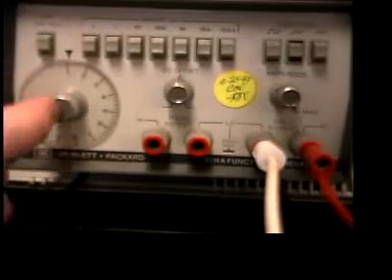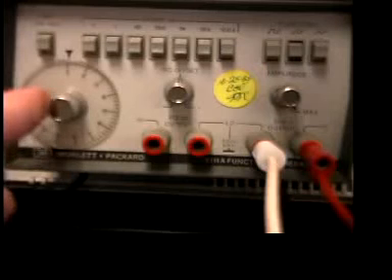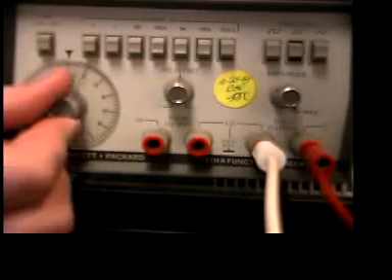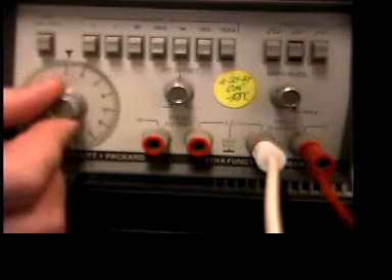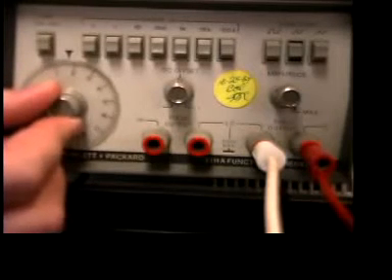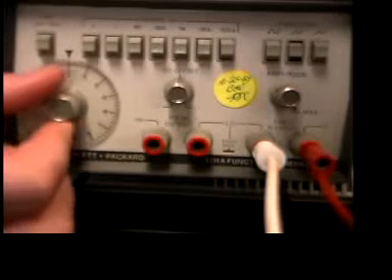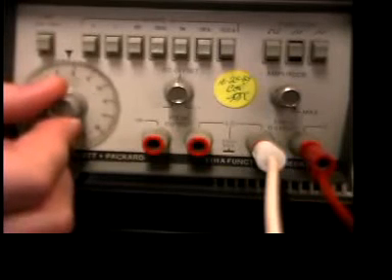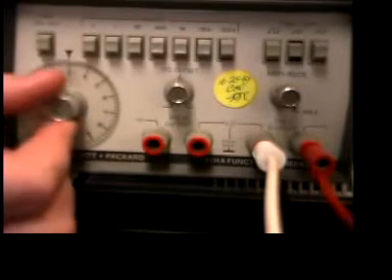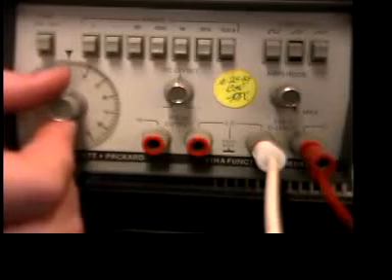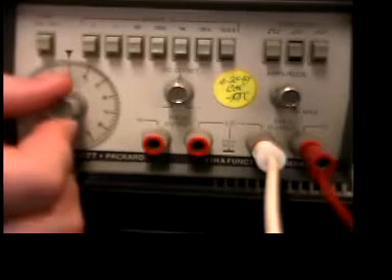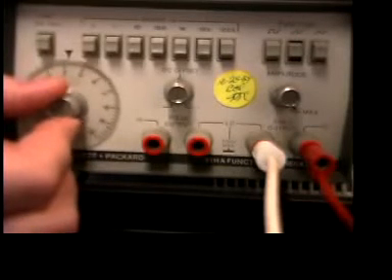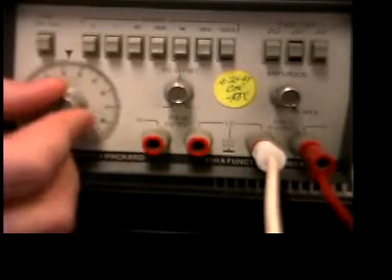You want the same person to adjust this during the experiment. You're going to adjust the frequency to the number 2 and take a reading. Adjust the frequency to 3,000. It should be 3,000 but what is it really? And then 4 and so on and so forth.